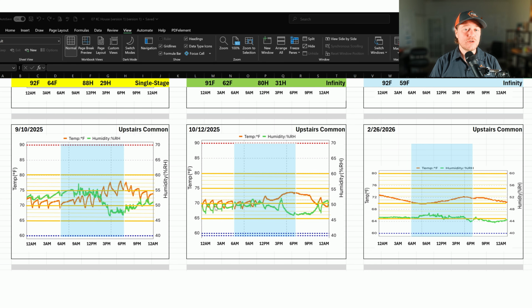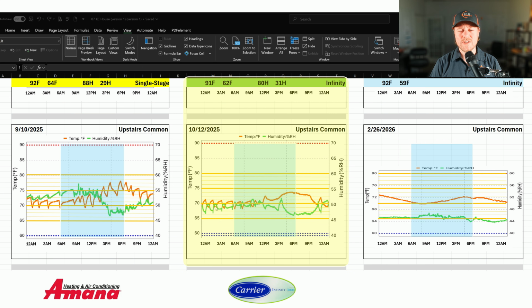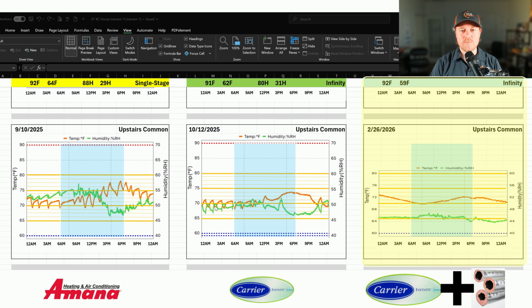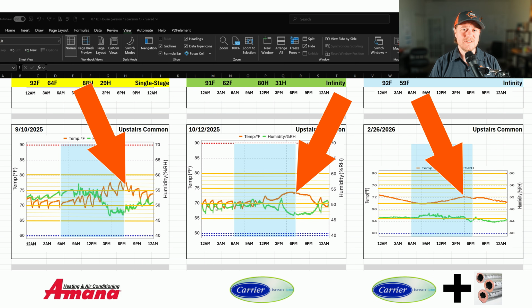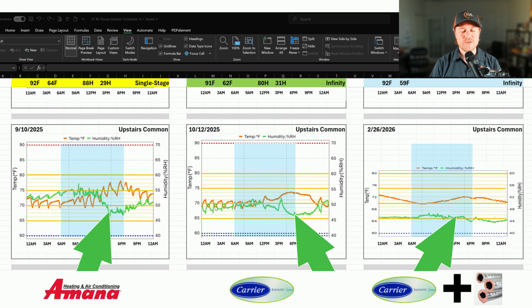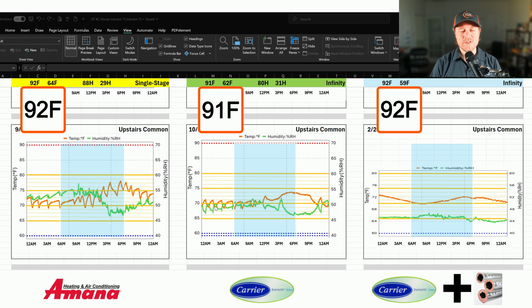What we're looking at here is our temperature and humidity data log reports. The first two here are our example of the HVAC system performing on the old ductwork. On September 10th, 2025 is when we were still running our single stage 4-ton Amana system. Then we changed it out to a fully variable Infinity system. We left all the ductwork alone just to see if the equipment alone could help improve our situation, which we're looking at here on October 12th. Then on February 26th, what we're looking at here is after all the ductwork modifications. The orange line is representing temperature, and the green line is representing humidity. All three of these days got up into the low 90s.